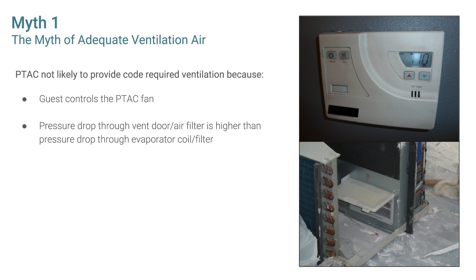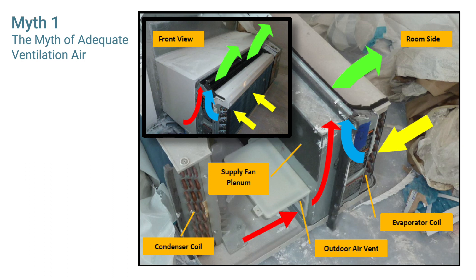Another issue is that the pressure drop through the vent door air filter is higher than the pressure drop through the evaporator coil and filter. The majority of PTAC manufacturers describe how the vent door may be open or closed but provide little or no guidance on the moisture impact of an open vent door. Their literature lacks clear direction even in warm humid climates and usually only addresses increased energy impacts, with an absence of cautionary notes on the increased risk of moisture problems from open vent doors.